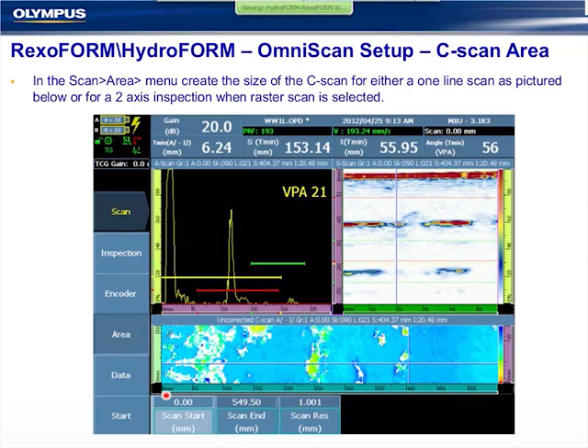If this were a two-axis scan, I would have 0 to whatever I programmed, and I would have the other axis here. So I'm scanning from 0 to 550 millimeters here, and this is mechanical. Every 1 millimeter the scanner travels, the software is recording every A scan for every aperture in this axis.